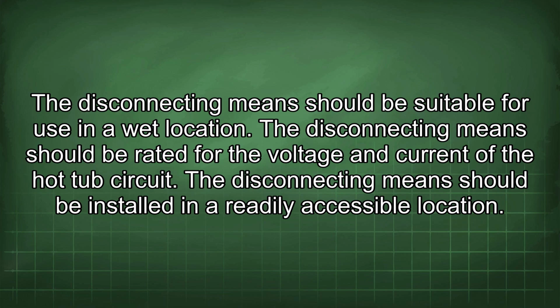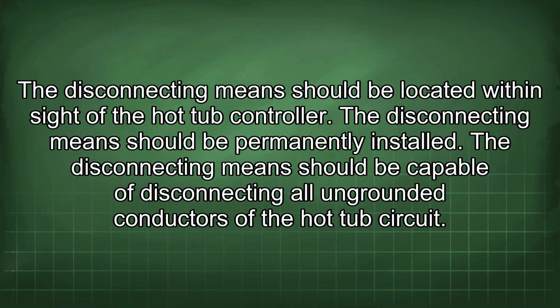The disconnecting means should be installed in a readily accessible location. The disconnecting means should be located within sight of the hot tub controller. The disconnecting means should be permanently installed. The disconnecting means should be capable of disconnecting all ungrounded conductors of the hot tub circuit.